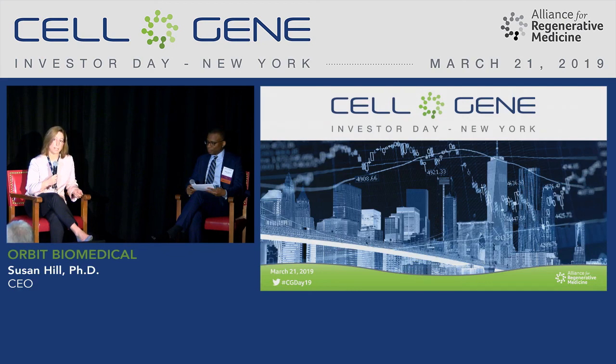And it generated some great data. So through that clinical data, we know that we can use the device to deliver successfully to the subretinal space. We know that it's possible to do it without removing the vitreous. We know that it doesn't pierce the retina. We also know that in that study there was no egress of cells out into the vitreous. And we also know from ongoing follow-up from the study that there's been no incidence of cataract from that study as well. So we have a really good foundation in terms of the safety data, and there were also learnings around the device and the training that came out of that too.